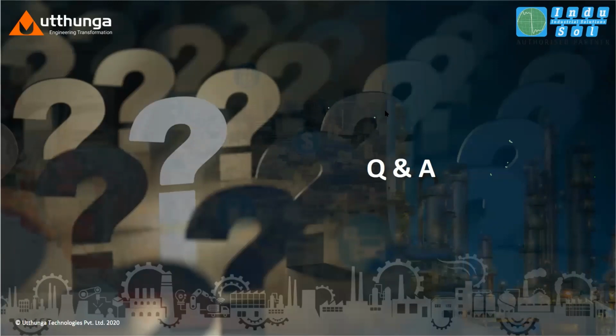Last question, Angad. After how many nodes is a repeater needed? After 31 nodes, we have to connect a repeater, because a repeater is also considered a node in the network, not as a slave, but as a node, because it is RS-485 communication. It is like energy flowing through the complete cable. If energy is flowing, it has to be grounded properly, as well as enhanced. Enhanced means you have to put in repeaters. So 31 nodes is recommended in a single segment.